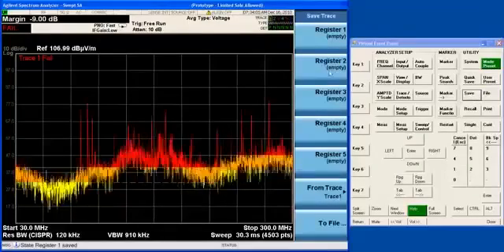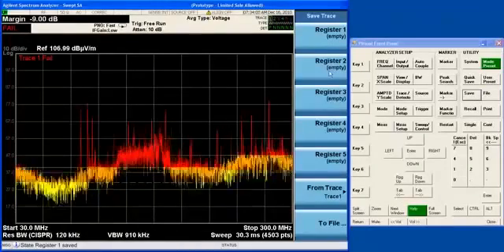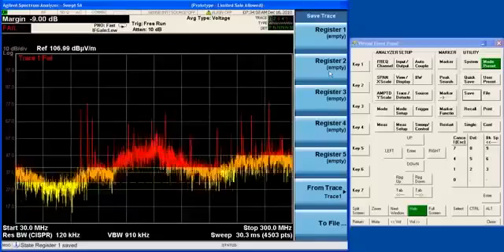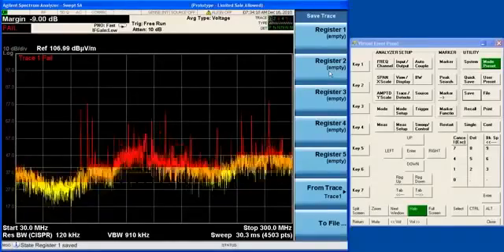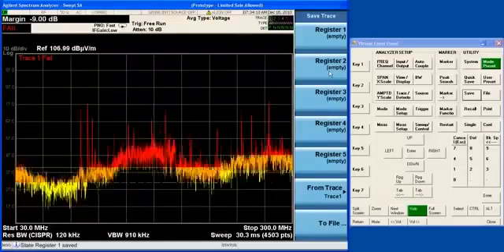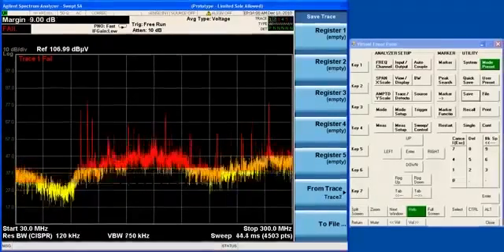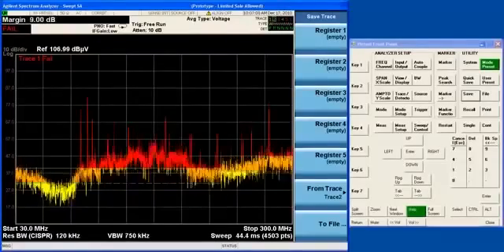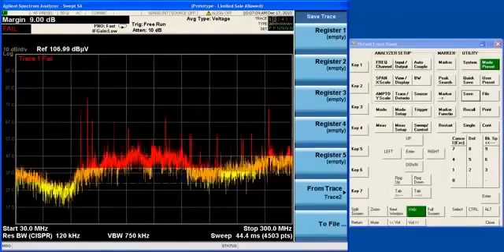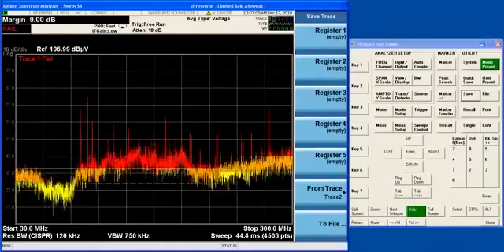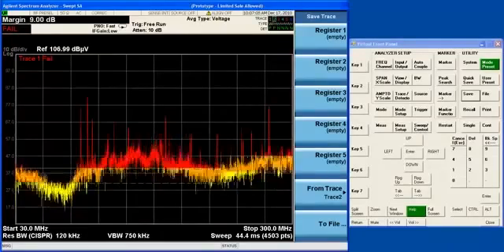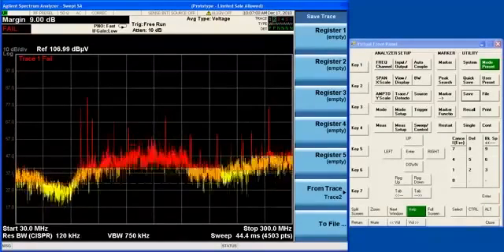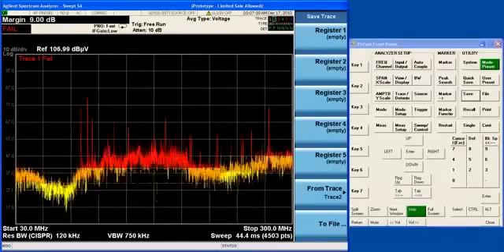With every trace save, you get the state of the analyzer. So when you load it back in, you will get all the settings back that you had when you saved the trace. So there is a quick look at the X-Series Spectrum Analyzer and some of the labor-saving features that it provides. Now let us go on and talk about the EMI Receiver app.